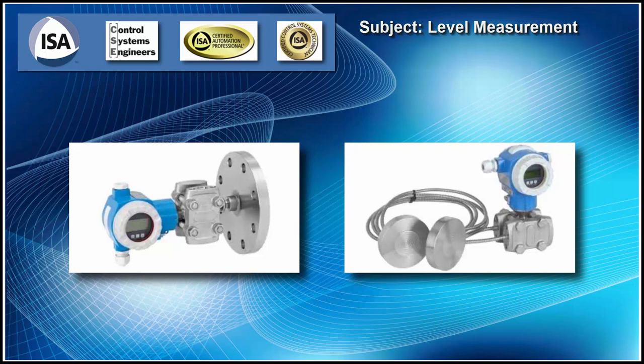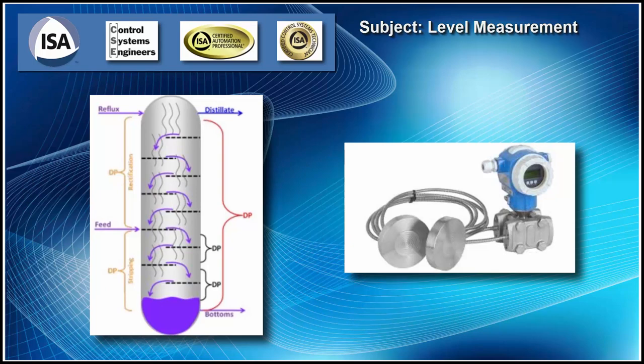The one on the right is a differential pressure transmitter, just like you see on the left, except we have diaphragms on it that are connected with capillary tubes. And we take this and we put it on a flange at the top and a flange at the bottom. And this is for measuring a differential pressure across the tank where it's pressurized. So like we talked about, we can measure the level with this. It's also used on a column where we want to see the differential pressure across the column and know what that pressure is to see if we're flooding or choking inside the column. And this will tell what's happening. And these will be attached in an area where there's no liquid. It's strictly clear vapor, a clear space with vapor.